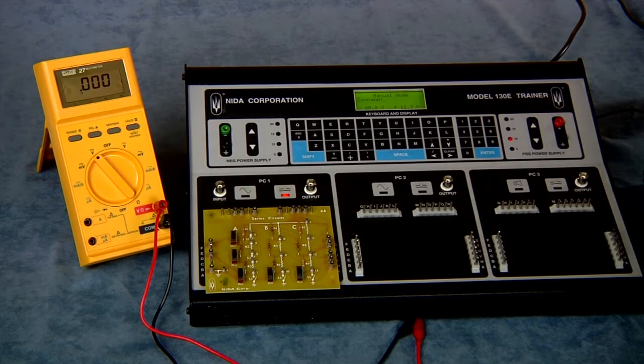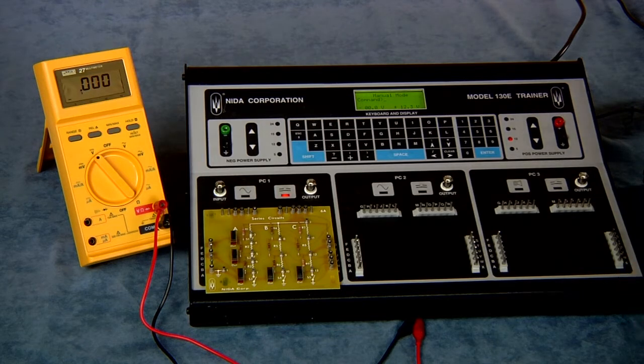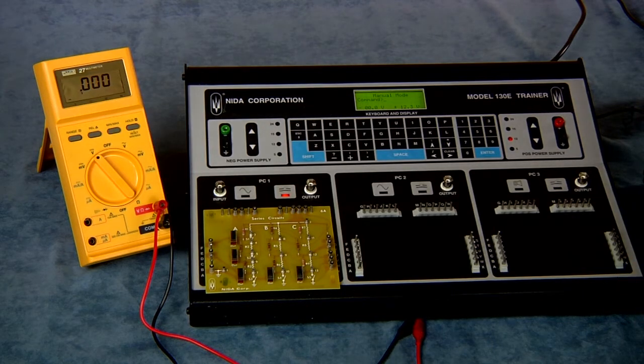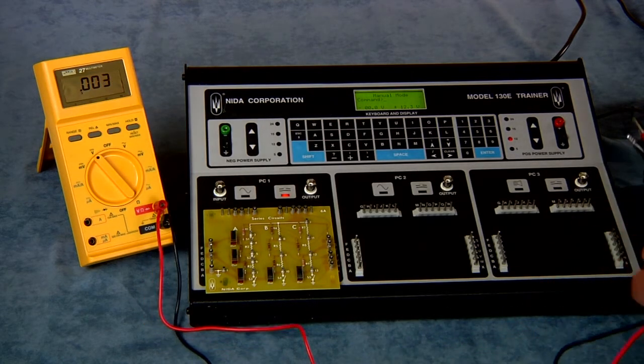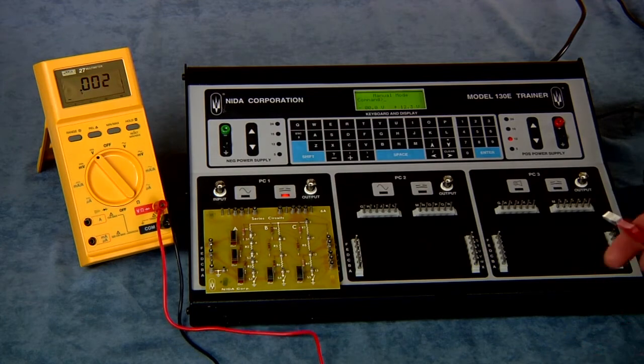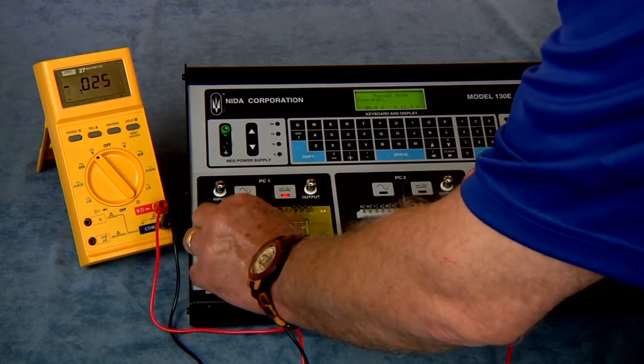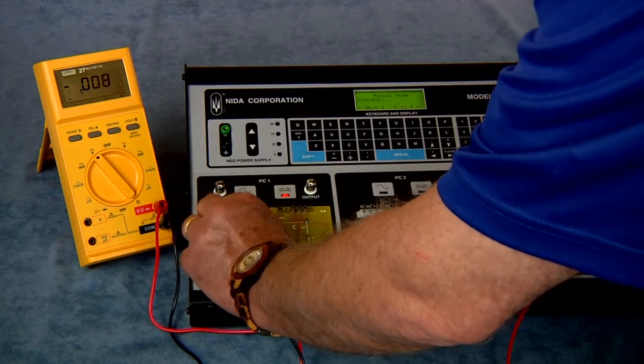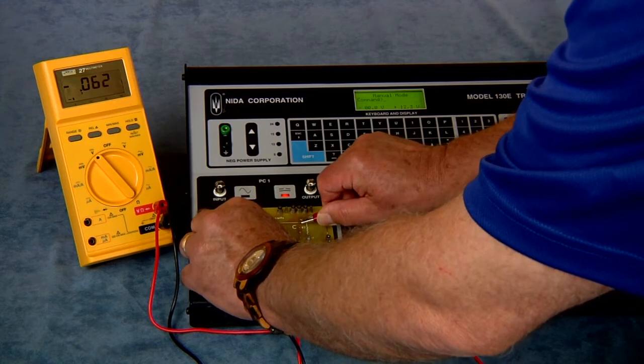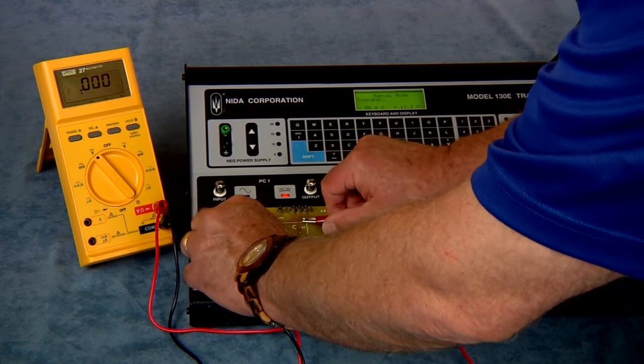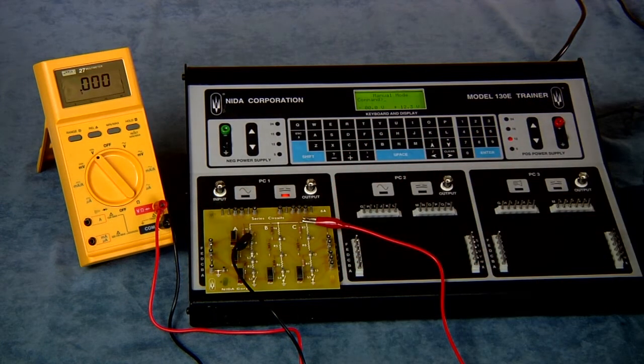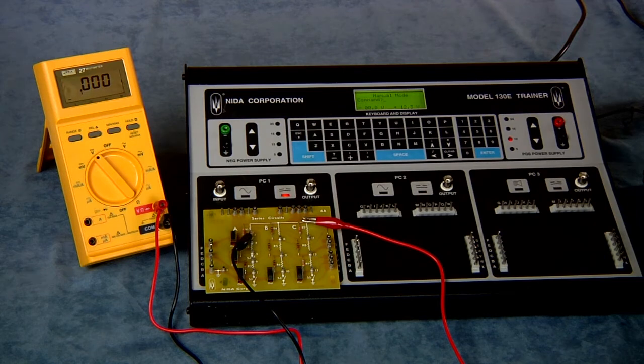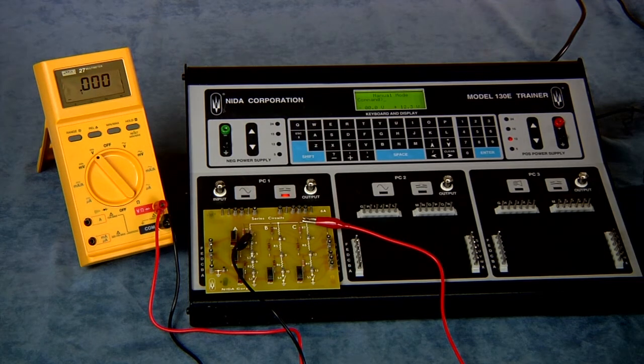So that's in the circuit. We'll now do the analysis of that simple series circuit. We'll go back to measure the voltage across test points two and three, and we can see that we have zero volts there. That's giving me an indication that there's something wrong with that circuit.